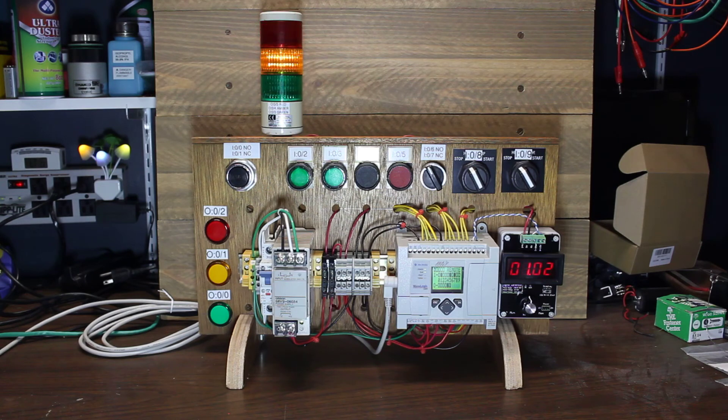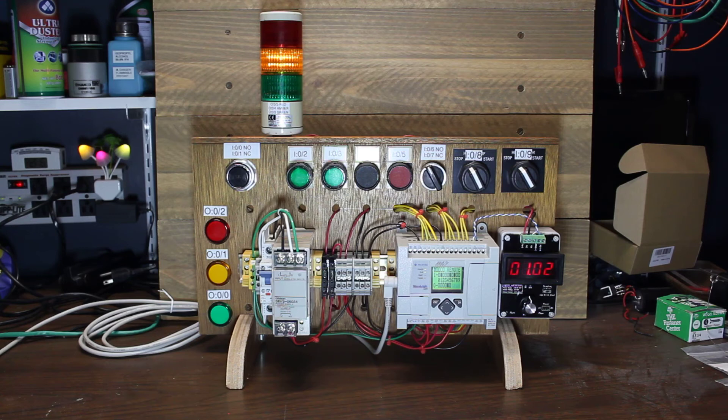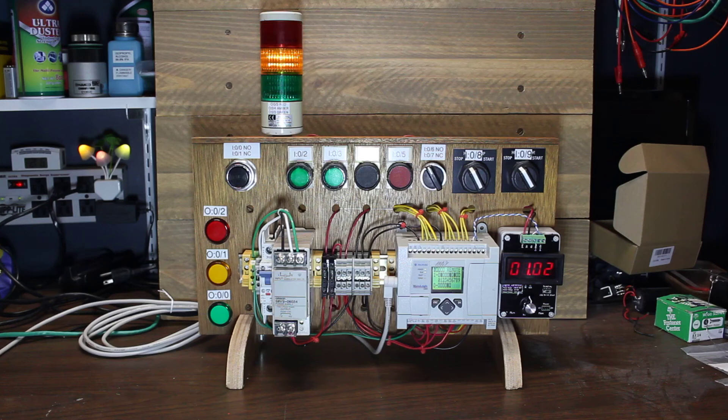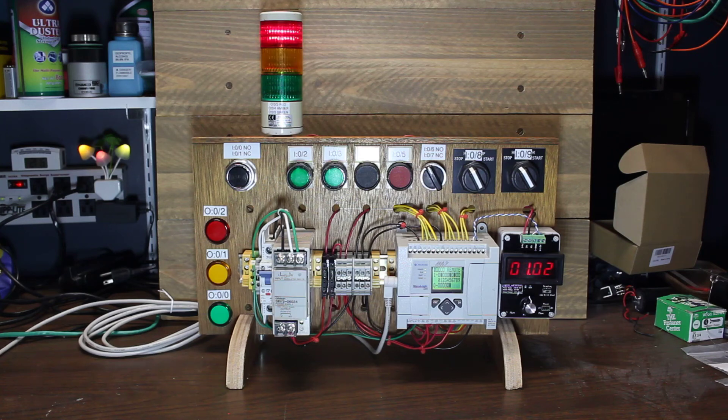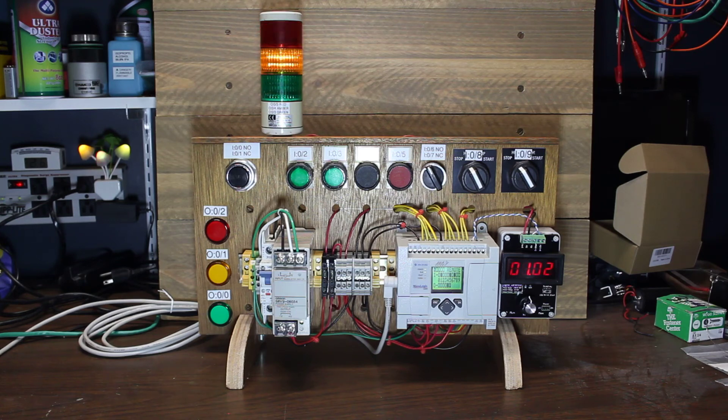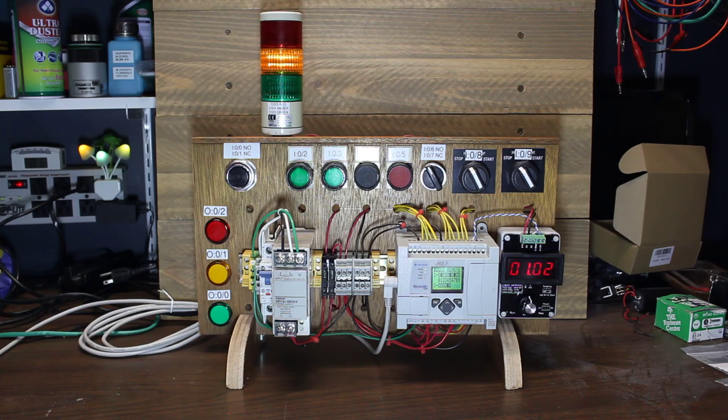The only place I used terminal blocks was where I needed to for power distribution. And all the IOs is directly wired between the indicators and switches and the PLC. You know other than that there's a couple fuses on the DC side. One for the PLC and one for the IO. And a breaker on the AC side of course.